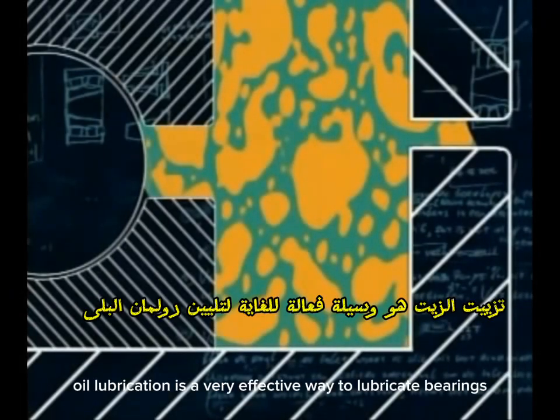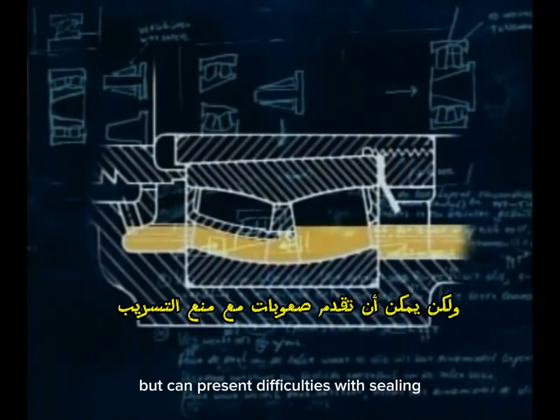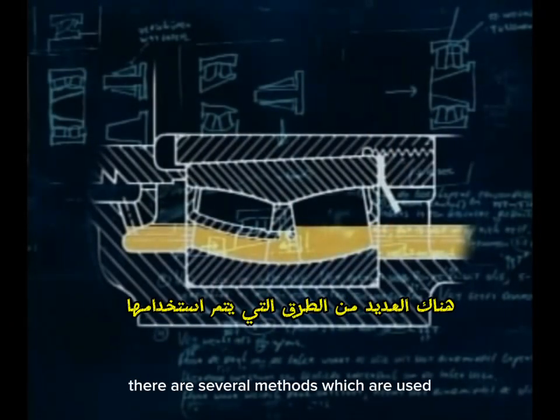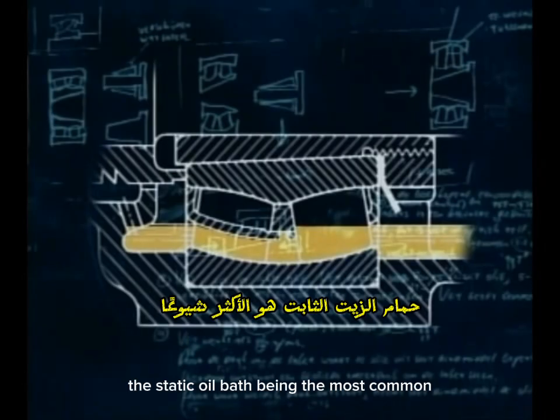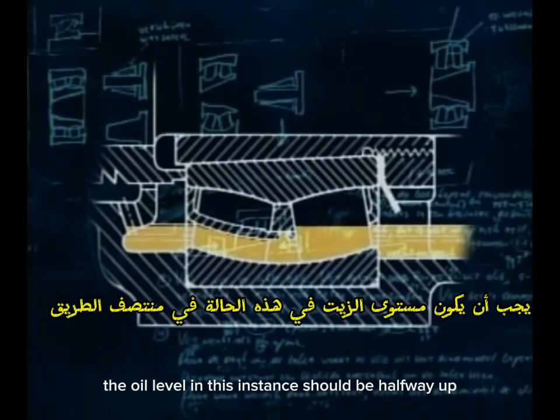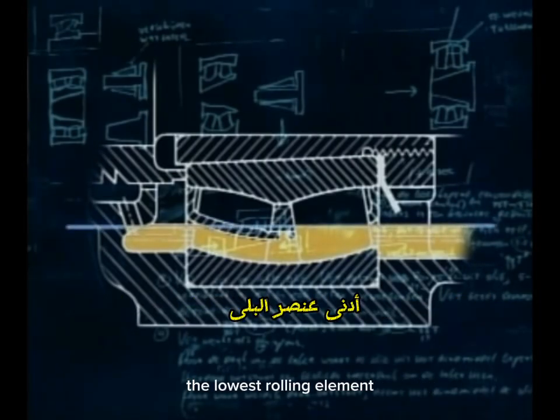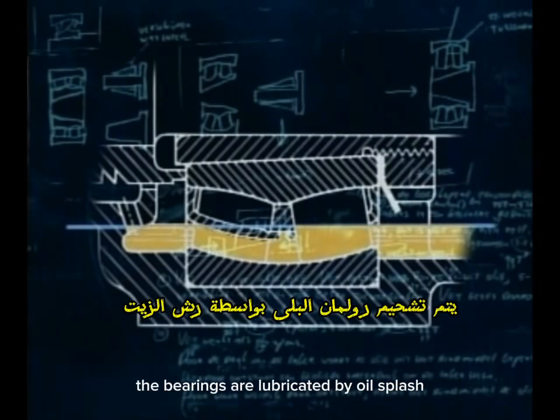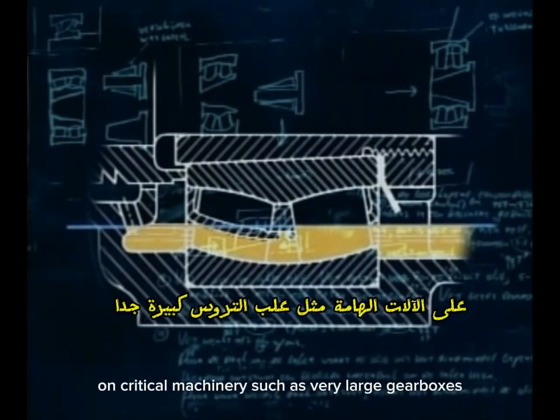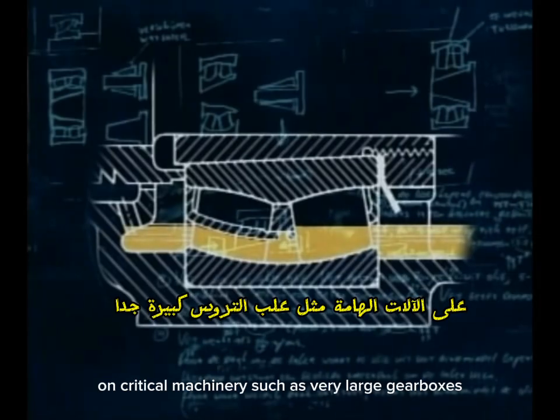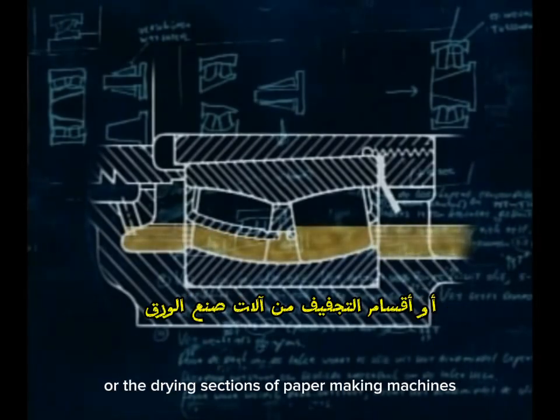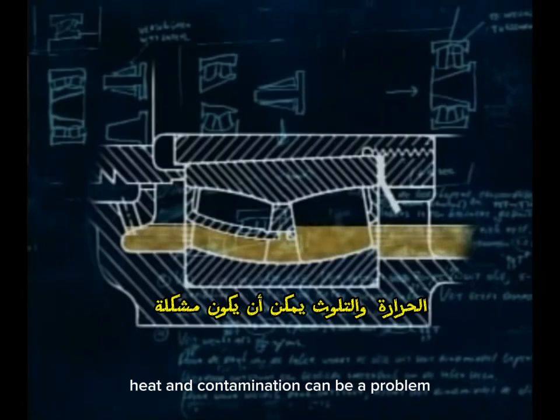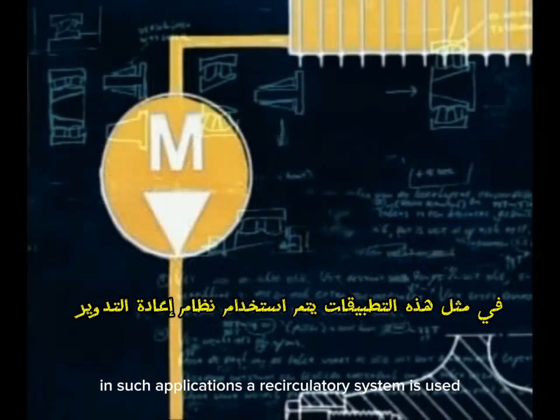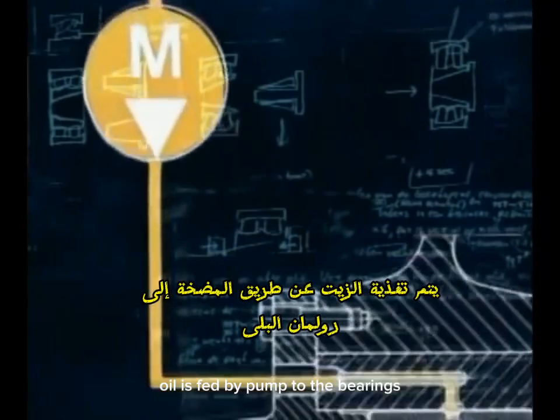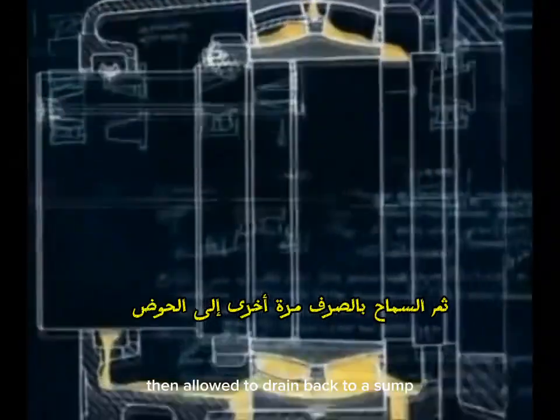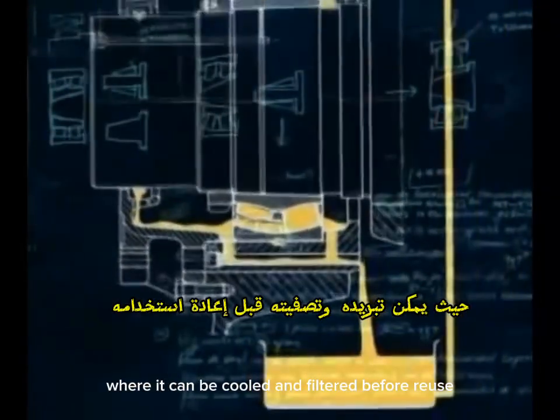Oil lubrication is a very effective way to lubricate bearings, but can present difficulties with sealing. There are several methods which are used, the static oil bath being the most common. The oil level in this instance should be halfway up the lowest rolling element. In most gearbox applications, the bearings are lubricated by oil splash. On critical machinery, such as very large gearboxes or the drying sections of paper-making machines, heat and contamination can be a problem. In such applications, a recirculatory system is used. Oil is fed by pump to the bearings, then allowed to drain back to a sump, where it can be cooled and filtered before reuse.